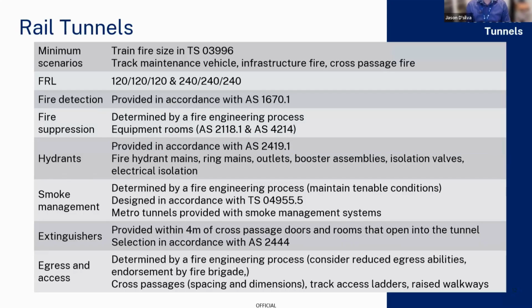Again, with our detection system, for those in Australia we follow AS 1670.1, the detection standard. This talks about where we need detection as a minimum, in what rooms, and why we need it. As for suppression systems, you might ask why suppression inside a rail tunnel - it's not the actual rail tunnel, but the ancillary rooms that service it. Whether you want a sprinkler system or another type of alternate suppression system, we're open to that, but the standard does require something like that.